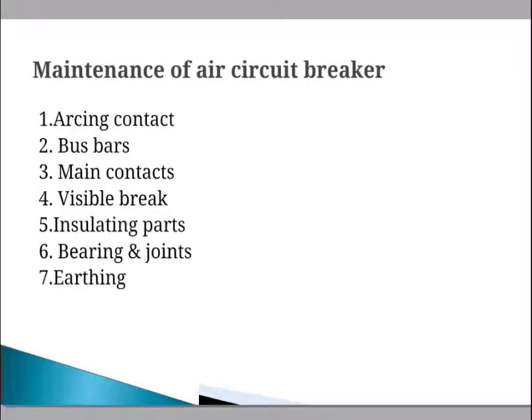For the visible break, clean with petrol and lubricate with Vaseline — carried out half-yearly. For bearings and joints, clean any rusted bearings and joints with petrol and re-grease with proper grease — carried out half-yearly.